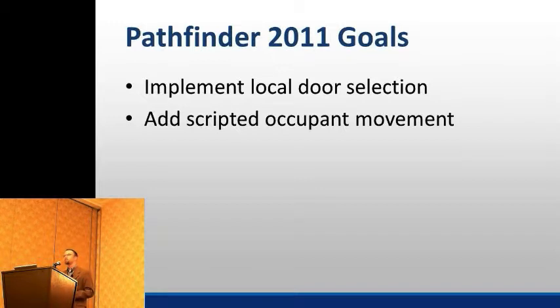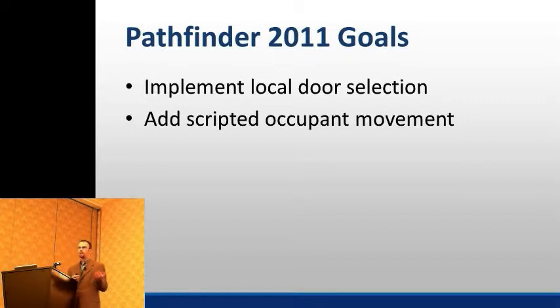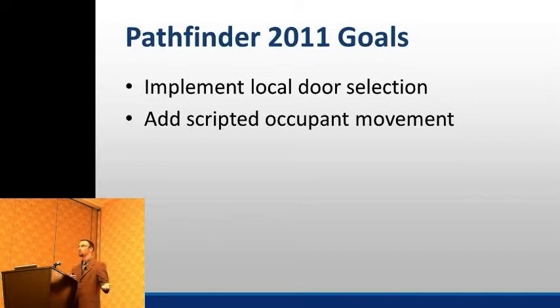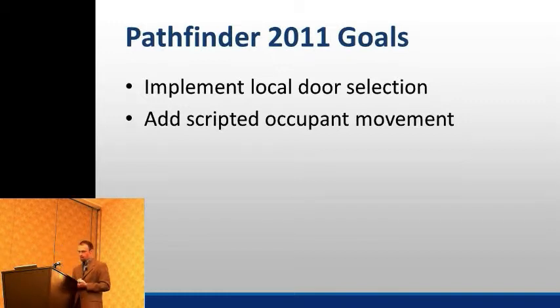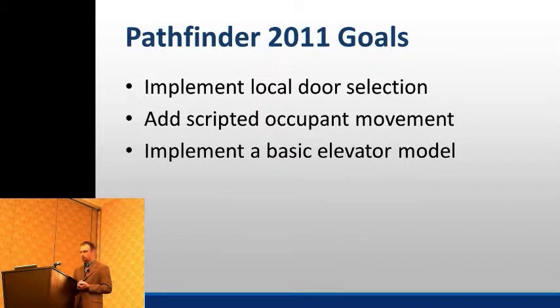We also wanted to add capabilities to script occupant movement rather than only having the choice of going to the closest exit. That would allow you to handle first responders entering a building, or to represent refuge floors where some occupants go to a certain location in the building and wait for a specified period of time, or then exit later. We also had a goal of implementing a basic elevator model, as elevators are becoming more and more relevant in evacuation, particularly for large high-rise buildings.